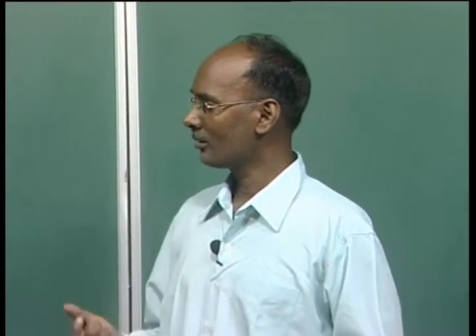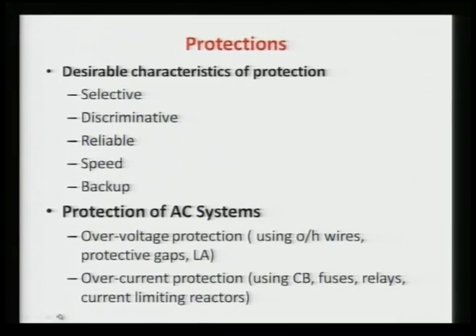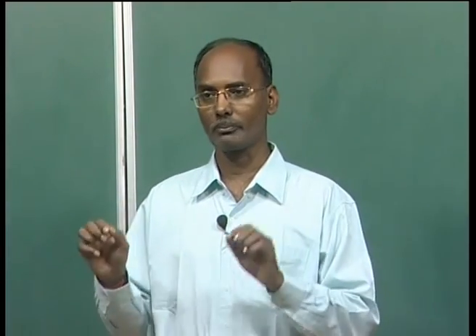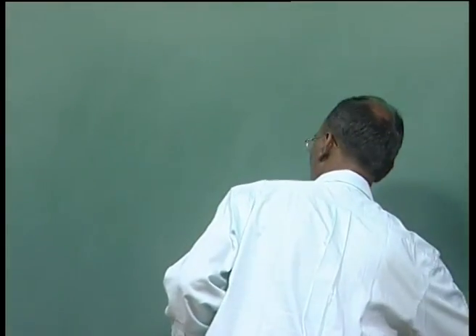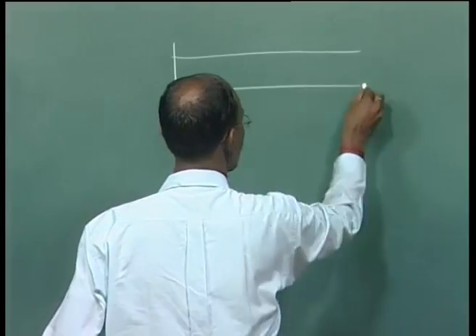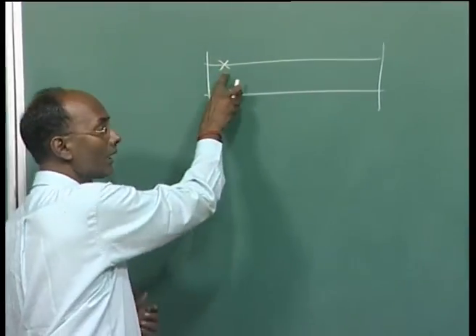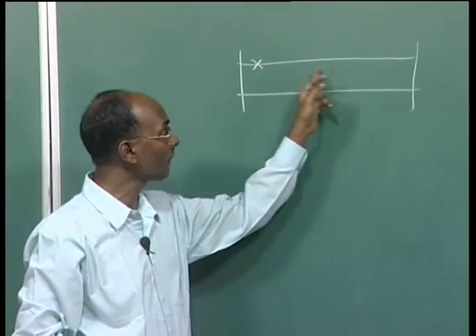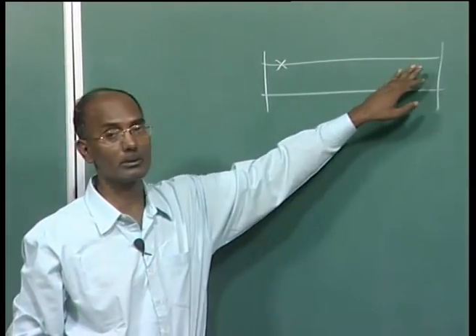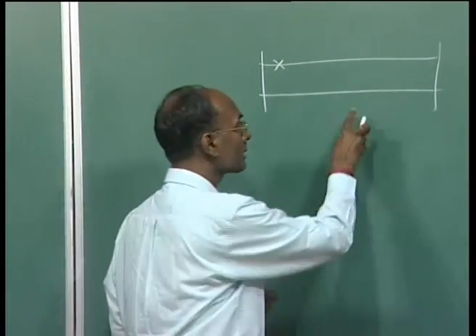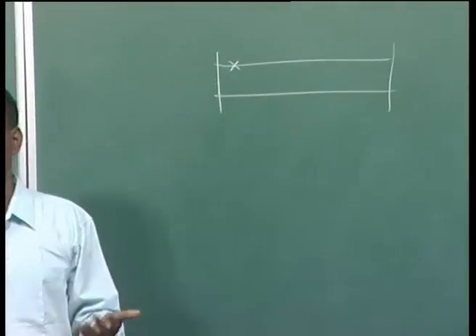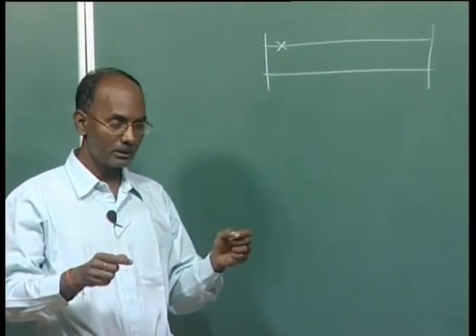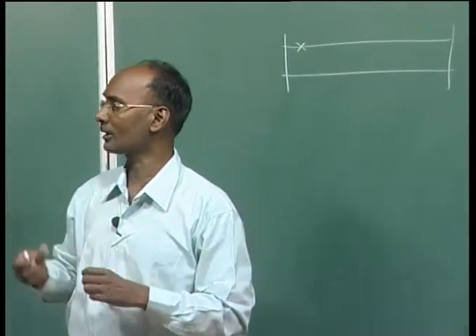Here, selective means that where the protection system is designed for a particular zone or particular apparatus, it should only operate if there is some problem in that zone or that apparatus. So it should be selective. If the disturbance is outside that zone, it should not operate. Let's suppose this is your bus and this is a line in the AC system, and this is your protection scheme. If this relay or protection scheme is designed for faults only in this line, it should only operate in this zone, so it is called selective. Whatever the disturbance outside of this zone, if it operates, then it is not selective. So it should select for which it is designed.